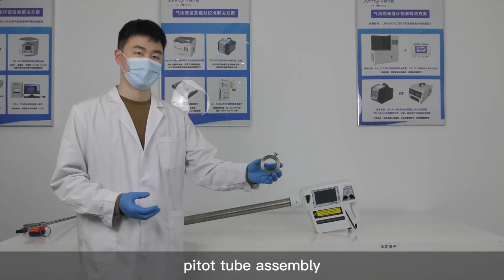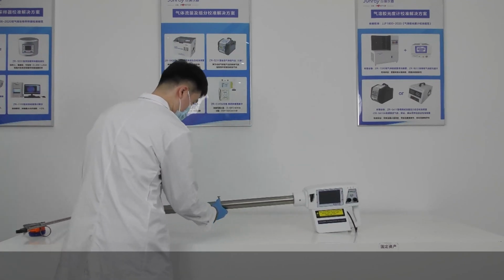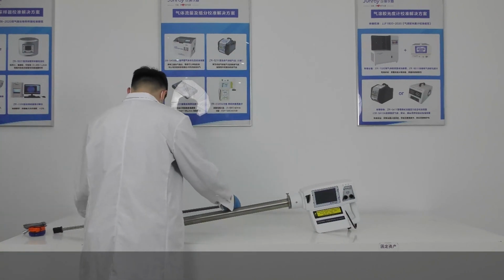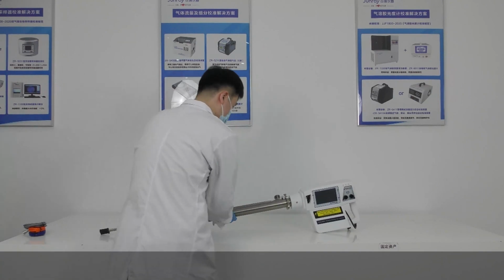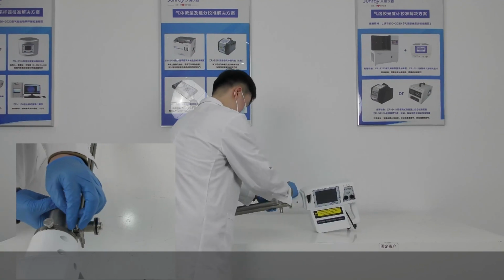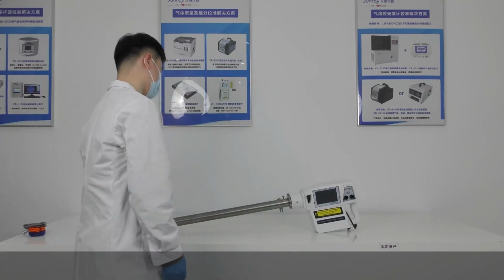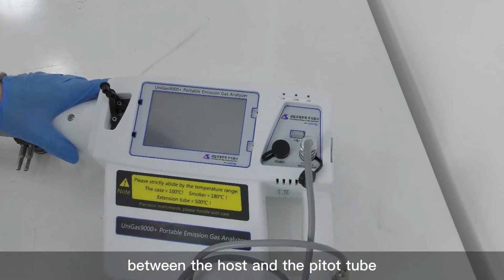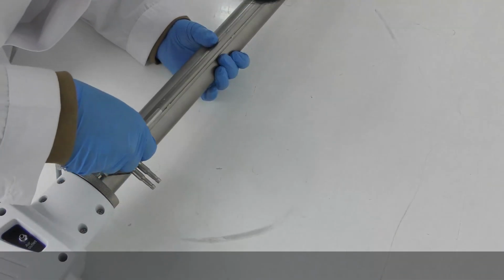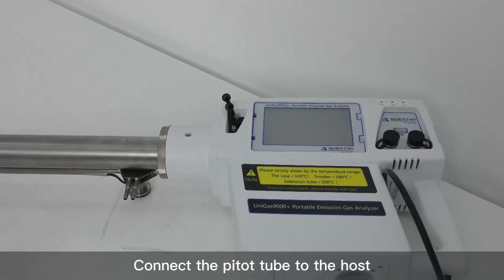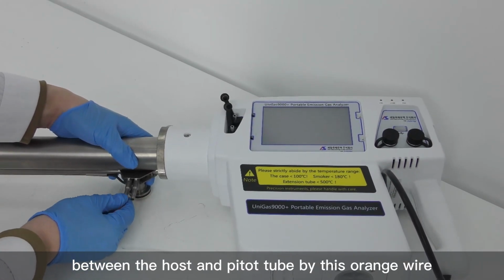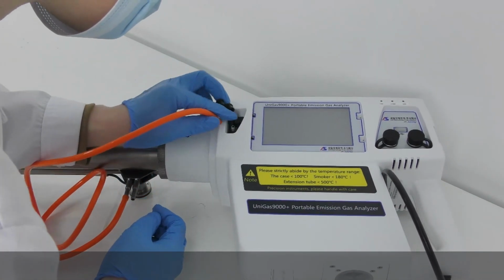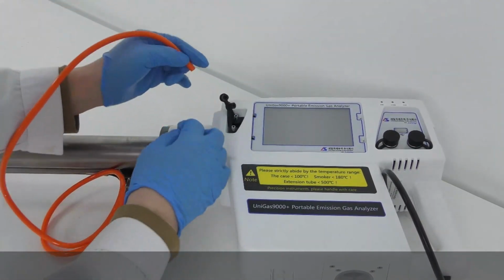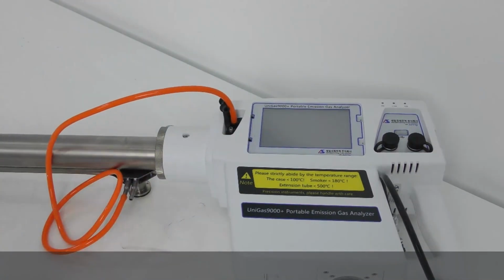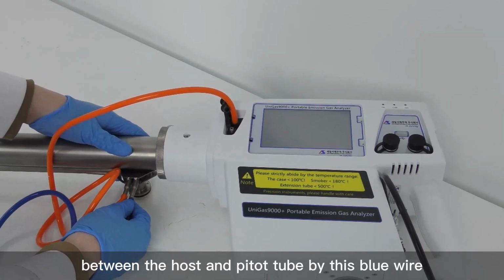Let us loosen the screw of the pitot tube assembly and insert the tube into the sampling tube. Then tighten the screw again. Connect temperature communication interfaces between the host and the pitot tube by this gray temperature wire. Connect the pitot tube to the host by this pressure flow hose. Connect the positive ends between the host and pitot tube by this orange wire. Connect the negative ends between the host and pitot tube by this blue wire.